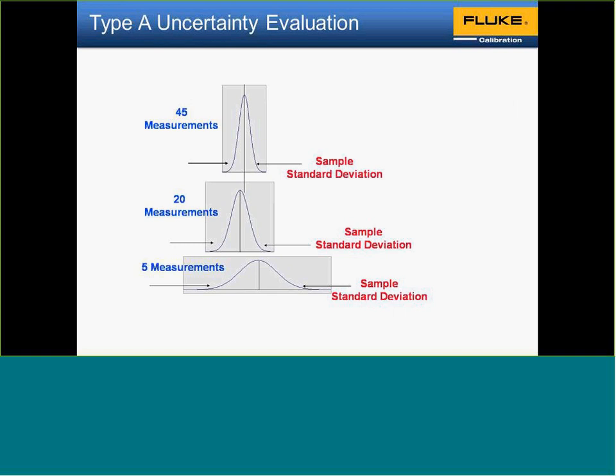I plan to represent how measurements and the degrees of freedom that you have can affect your uncertainty. And you see at the bottom, with 5 measurements, I have a wide spread for my uncertainty, as that bell curve just becomes clearer. So the more measurements you make, the better, and hopefully the smaller the uncertainty you will have.